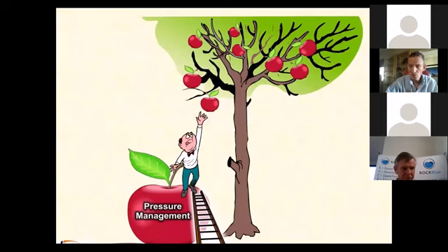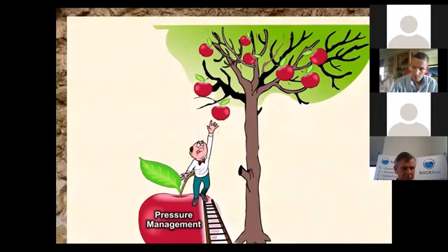It will not always work. I'm not saying it's the silver bullet for leakage in a system, but where it works, it will often give you spectacular results, and at the very least, it will prolong the life of your reticulation system. If you work out the value of that, you'll often find that extending the life of your system by 5 or 10 years has a far higher value than the water that you're saving. And it's generally not taken into account in the financial model.